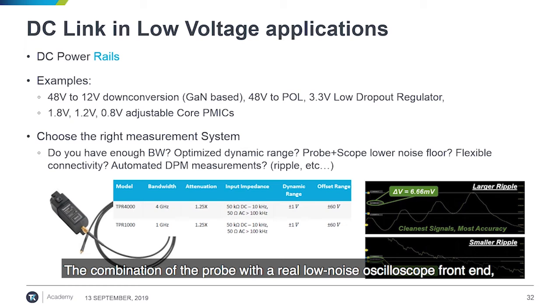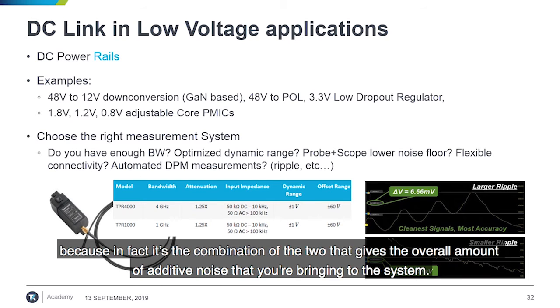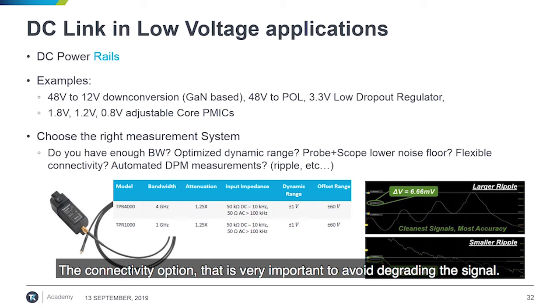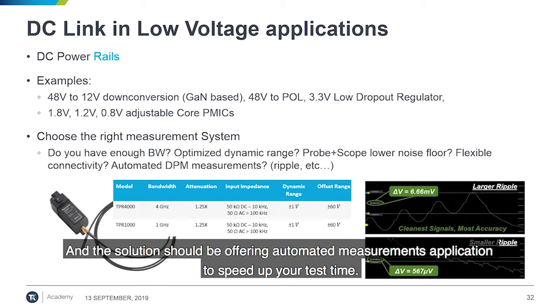So the recommendation is to consider three aspects: the combination of the probe with a real low noise oscilloscope front end, because it's the combination of the two that gives you the overall additive noise brought to the system; the connectivity option, very important to avoid signal degradation; and the software part, because the solution should offer automated measurement applications to speed up your test time.